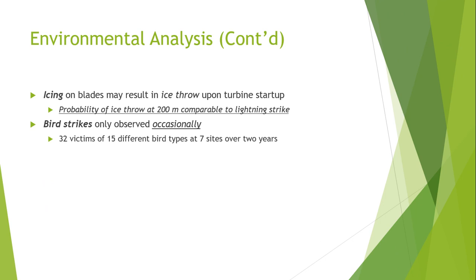There is an effect known as ice throw. Under certain meteorological conditions, icing may occur at the blades of the wind turbine, which may become loose or fall off during startup. The risk of icing mainly depends on the respective site conditions — for example, low or high mountain ranges. The risk of ice throw at a distance of approximately 200 meters is comparatively low and almost equal to that of a lightning stroke.